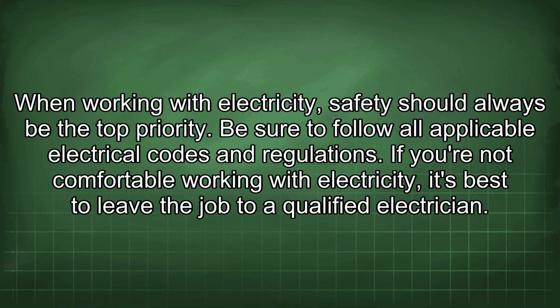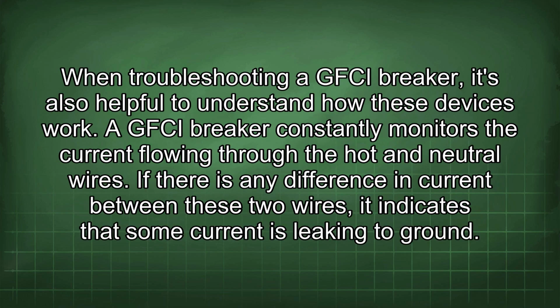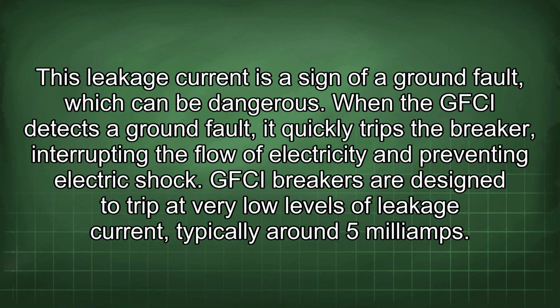When working with electricity, safety should always be the top priority. Be sure to follow all applicable electrical codes and regulations. If you're not comfortable working with electricity, it's best to leave the job to a qualified electrician. When troubleshooting a GFCI breaker, it's also helpful to understand how these devices work. A GFCI breaker constantly monitors the current flowing through the hot and neutral wires. If there is any difference in current between these two wires, it indicates that some current is leaking to ground. This leakage current is a sign of a ground fault, which can be dangerous.